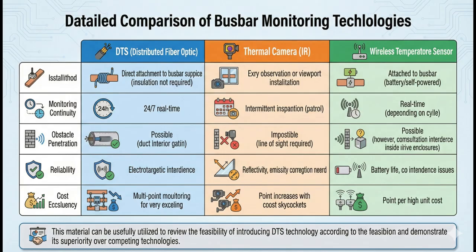In a busbar monitoring comparison, DTS is evaluated alongside thermography and wireless temperature sensors. Thermography is mainly for visible areas and periodic checks. Wireless sensors are fast to install but have limitations related to communications, power, EMI variables, and point scalability. DTS, when properly designed, can continuously monitor, including connection points, and offers strong reliability and scalability. The conclusion is that continuous, data-driven monitoring is the key to Busbar safety, not one-time inspections.